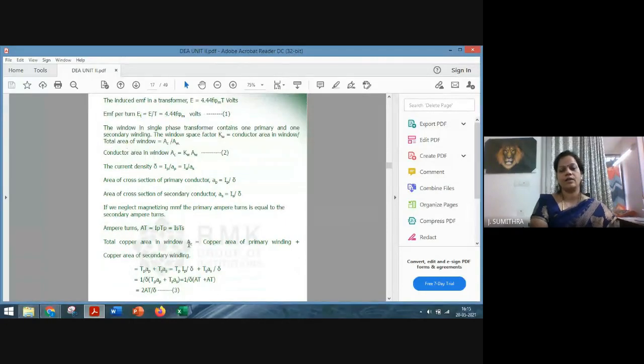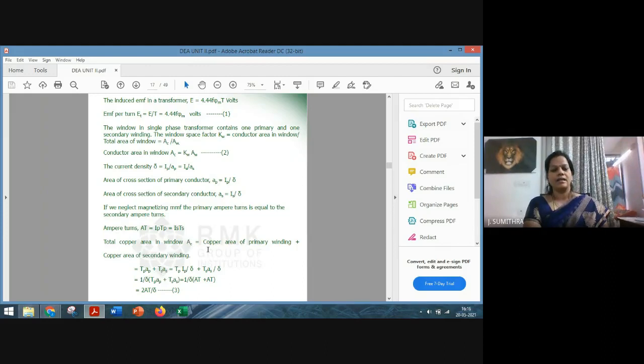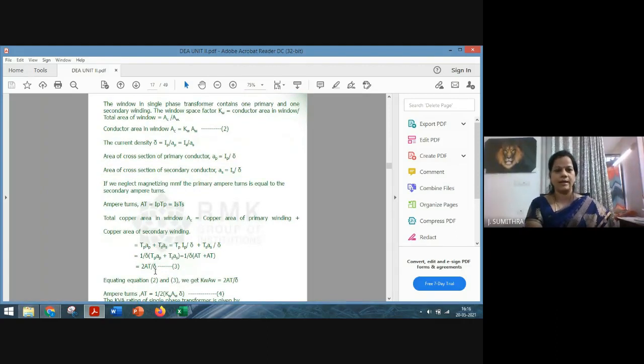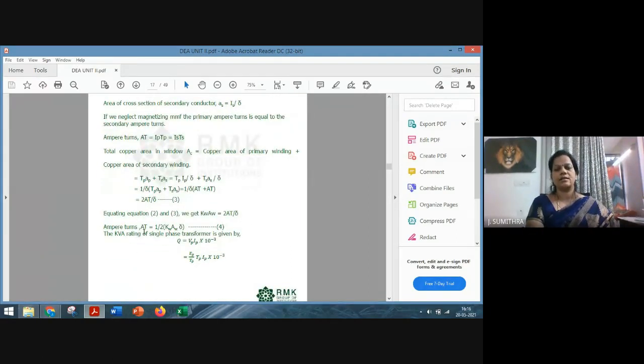Continuing with the derivation, the total copper area in the window equals the copper area of the primary winding plus the copper area of the secondary winding. The primary winding copper area is T_p × A_p and the secondary is T_s × A_s. Replacing A_p = I_p / δ and A_s = I_s / δ, I arrive at an expression for the total copper area as 2 × AT / δ. Since both expressions equal the total copper area in the window, equating them gives: AT = (1/2) × K_w × A_w × δ.